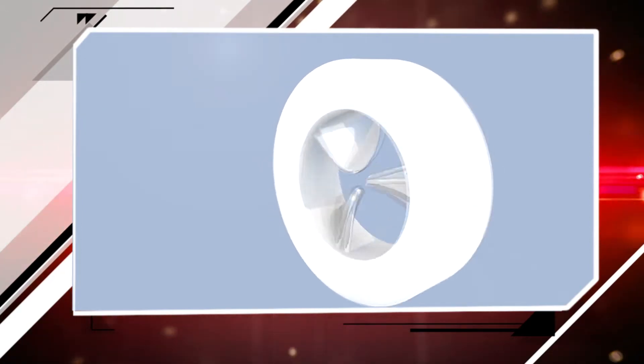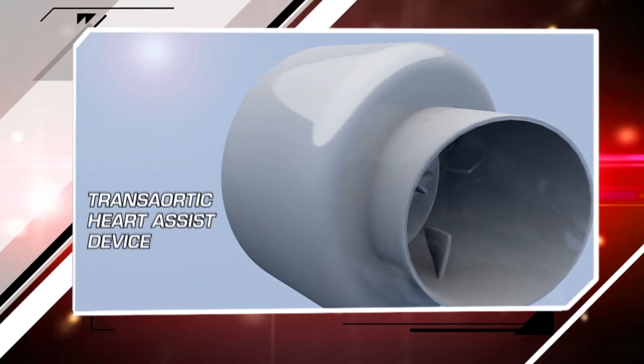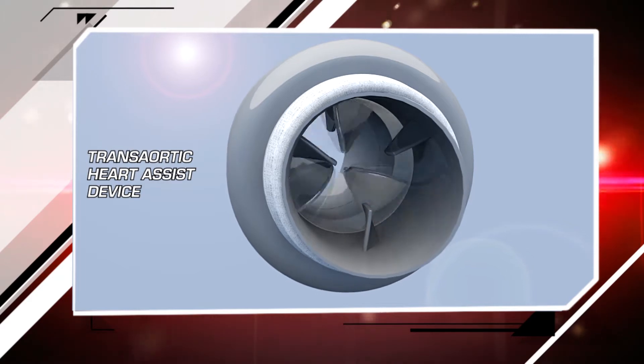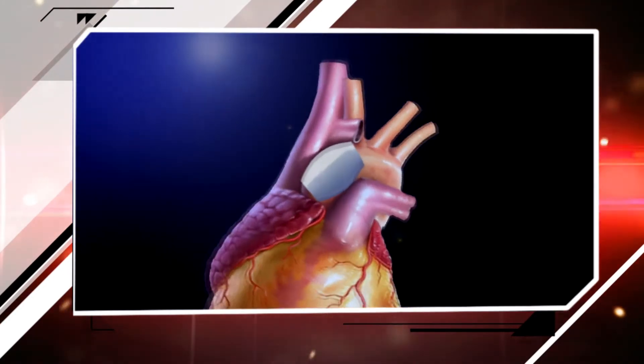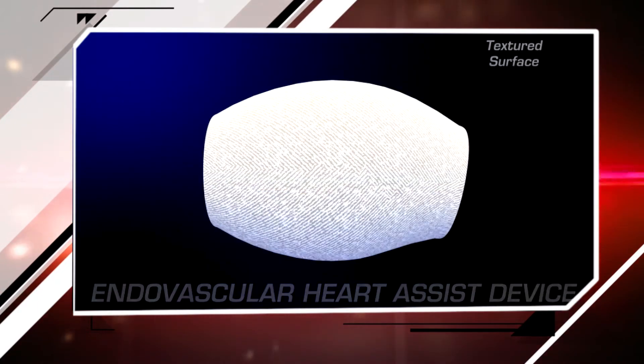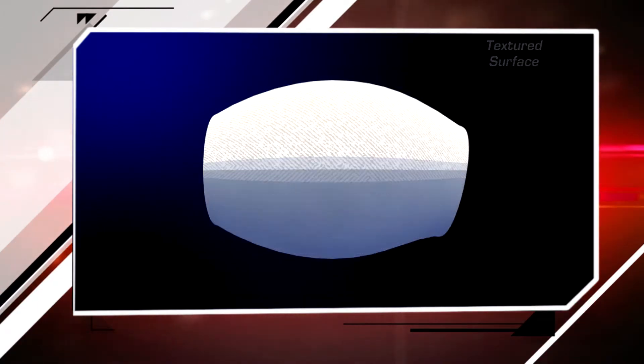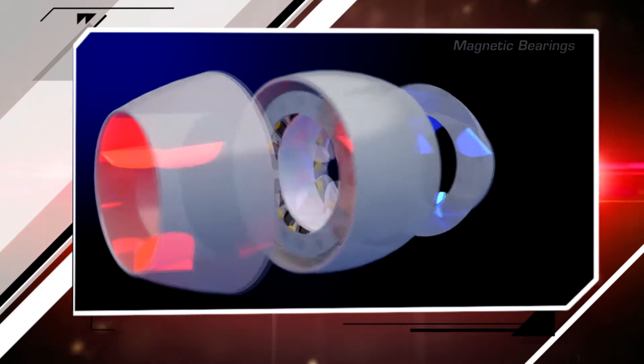This invention is an electrical device and a type of rotary blood pump, or mechanical heart pump. The motors in the device are brushless and synchronous electric motors, in which direct drive technology is used. The device contains rotors rotating on a magnetic bearing with no shafts. With their special design, the rotors have no surface contact.